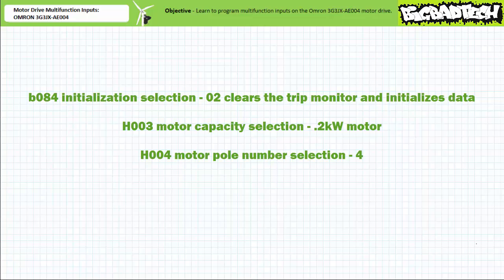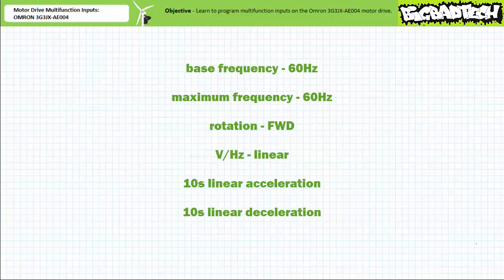Due to space constraints, we won't be using an external speed potentiometer input for this exercise, but rather using the frequency adjustment knob in the digital operator group. This start state establishes a 60 hertz base frequency, a 60 hertz maximum frequency, forward default rotation, a linear volts per hertz ratio, a 10 second linear acceleration, and a 10 second linear deceleration time, among other properties. Given this start state, the motor drive is now ready for today's activities.